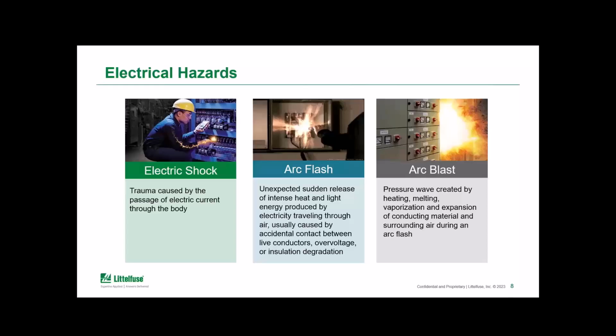Next, we have arc flash, which is that sudden explosion of intense heat and light energy that can really cause devastating damage and injury to any equipment or personnel that happen to be in the path. Of course, there are many calculations and codes and standards that have been developed, and software tools, to help take steps to protect against and understand and mitigate and reduce the arc flash energies, which is excellent. And last, we have arc blast. So this is the pressure wave that's created as the result of a thermal expansion during an arc flash. And in some cases, depending on the equipment, this can be just as dangerous as the arc flash itself.